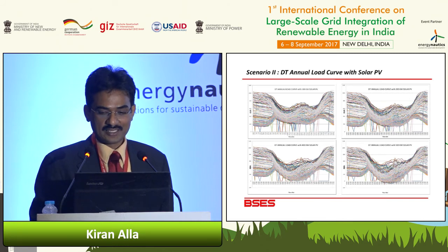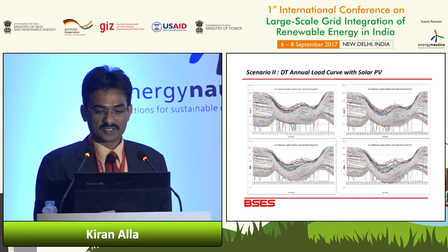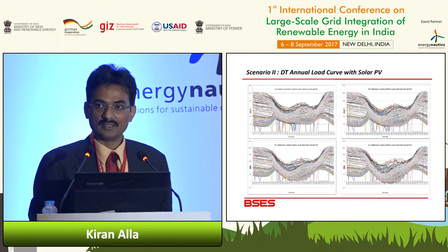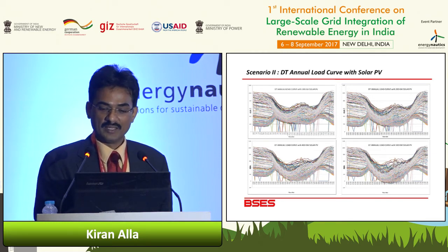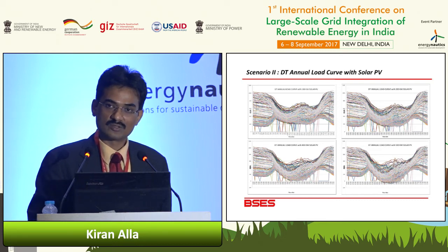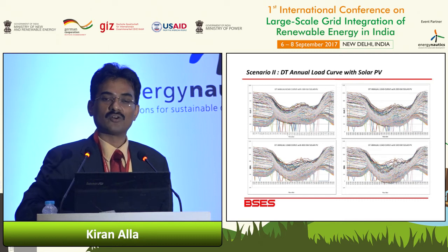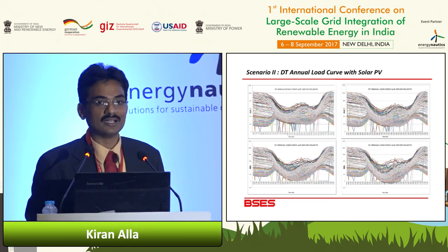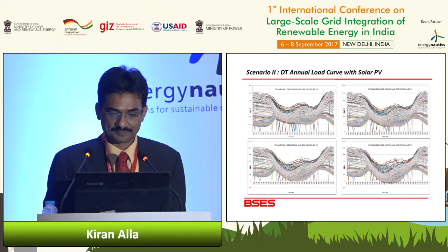Even with 50% penetration, there are very few cases where we see reversal of power flow. The benefit is that we can avoid reversal of power flow from the distribution transformer, meaning power will not go to the 11 kV level but gets absorbed at the LT level, which minimizes the losses.